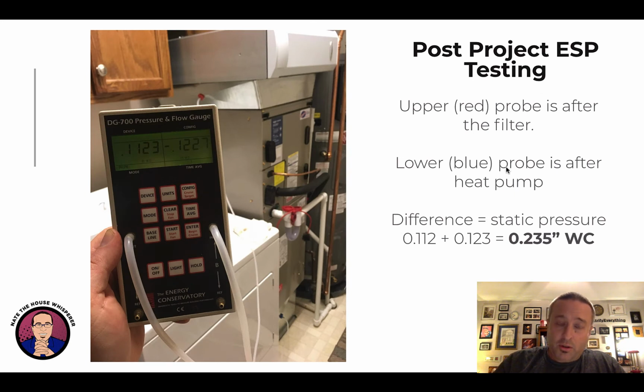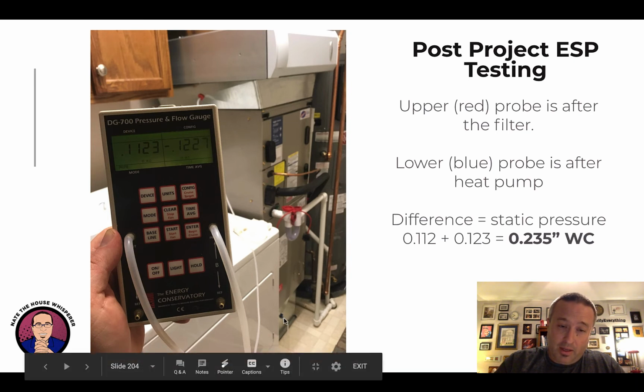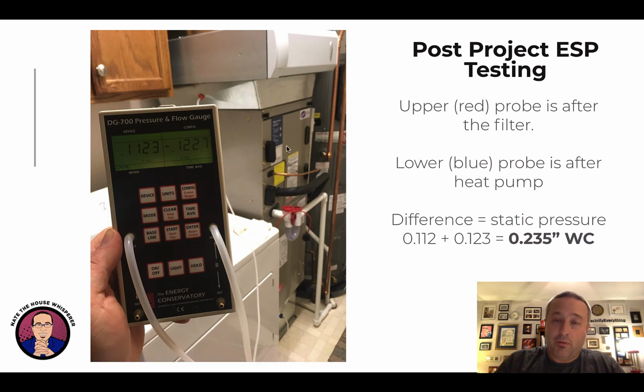So post install, now this is a 2-ton heat pump, and it's actually oversized for this house. The model didn't say it was, but I wondered if it might be, because it's a condo with a shared wall. It's oversized, I've watched the thing run. But now here we are again, here's the red probe going in. This is the big filter right here, so it's after the filter. And you can see the blue probe down here, that's after the whole heat pump unit. The heat pump has one fewer thing in it, there's no furnace in this, it's just a coil like your air conditioner and then a fan.